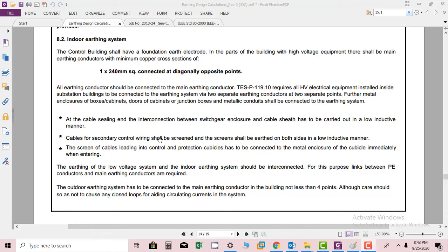Hi friends, in this section we will discuss indoor earthing system. The control building shall have a foundation electrode. In the part of building with high voltage equipment there shall be main earthing conductor with minimum copper cross-section of 1 x 240mm sq. connected diagonally opposite points.